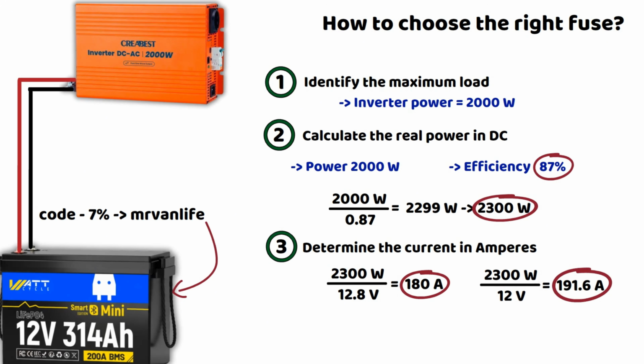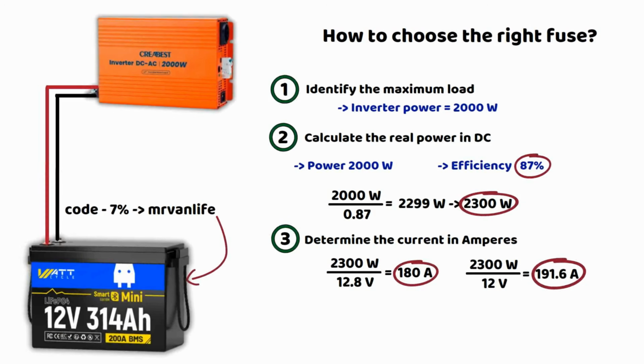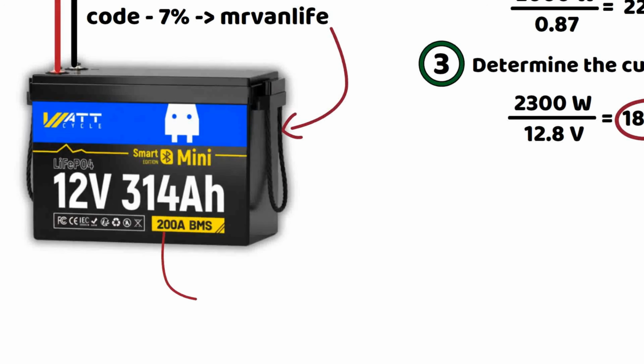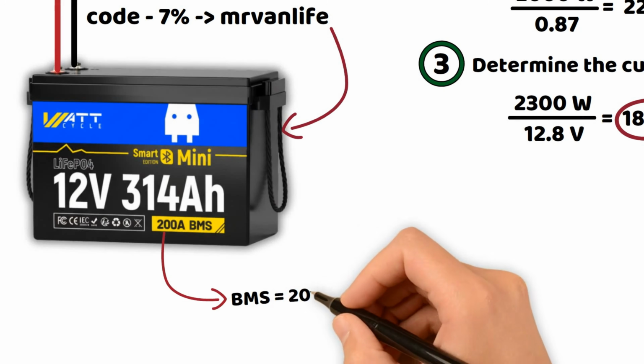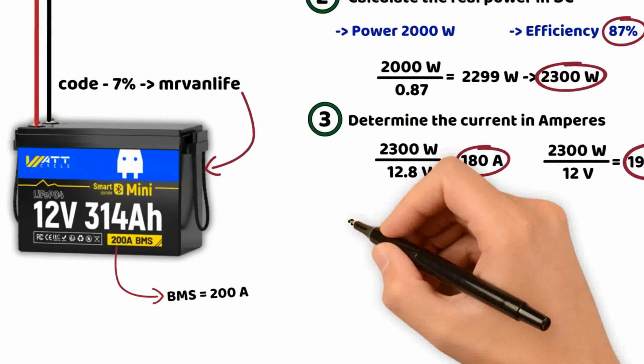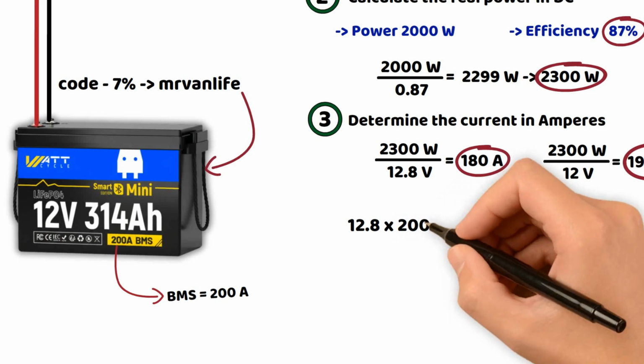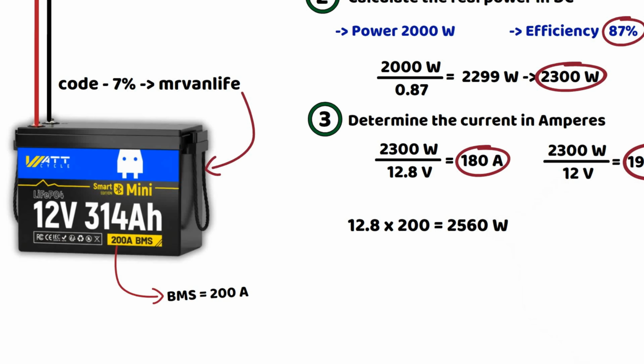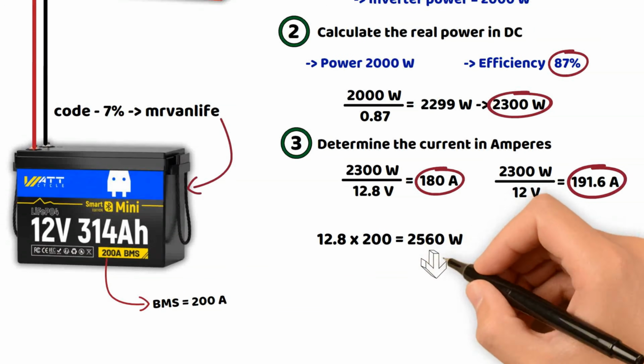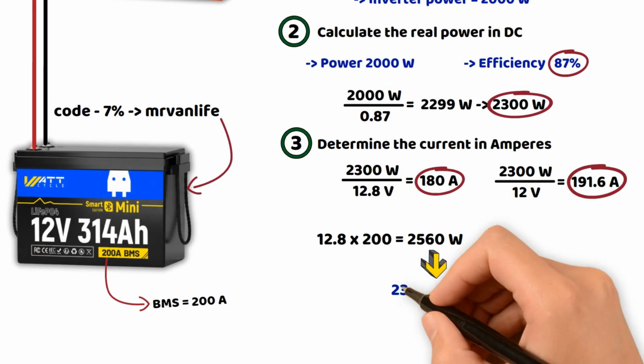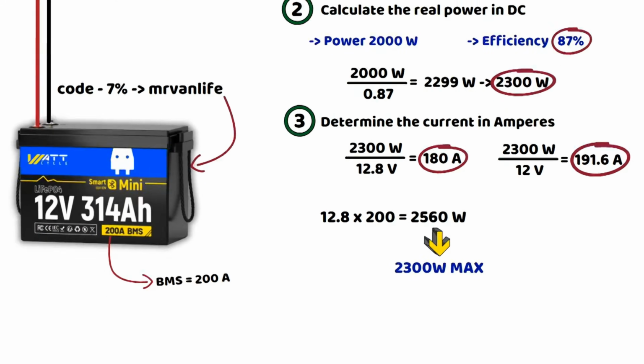Now we also need to check that our battery can handle a nominal current of this value. On the WattCycle battery we have a BMS rated at 200 amperes. 12.8 times 200 equals 2560 watts. We remain above the power demanded by our converter. Loss is included in the calculation. We're close to the limit, but in practice we'll have a margin of about 15 to 20 amperes.